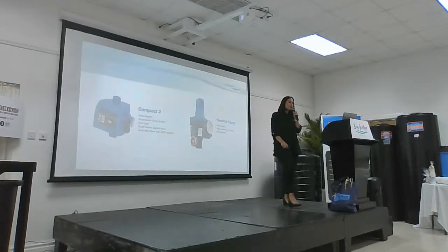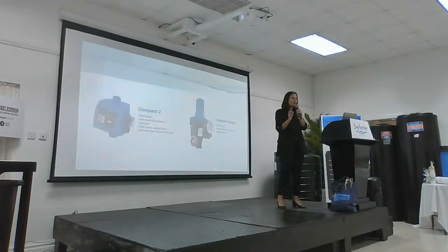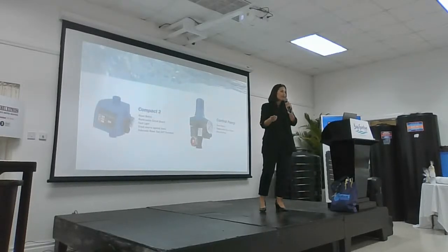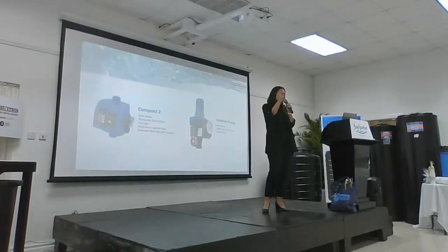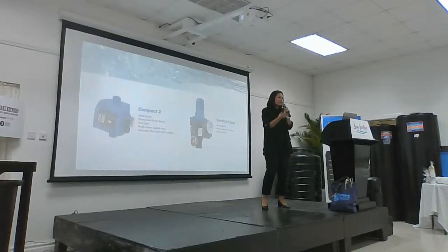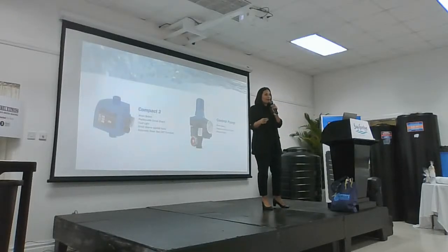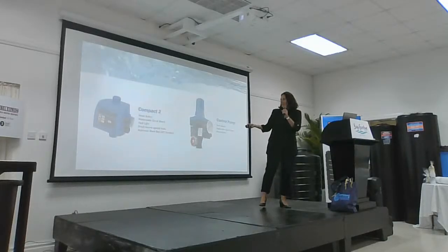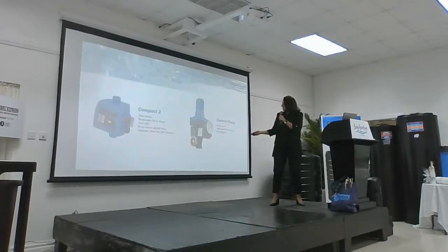And in the new model that's coming later on this year, they've actually integrated an incredible feature. When your pump hasn't been in operation for 72 hours, or 3 days, it automatically kicks on your pump and lets it run for a couple of minutes. What that does is ensure that your shaft seal doesn't stick and the impellers are running. It's going to reduce the need for maintenance in the long run. So trust me, we'll do a great announcement as soon as it arrives, and we'll let you know.